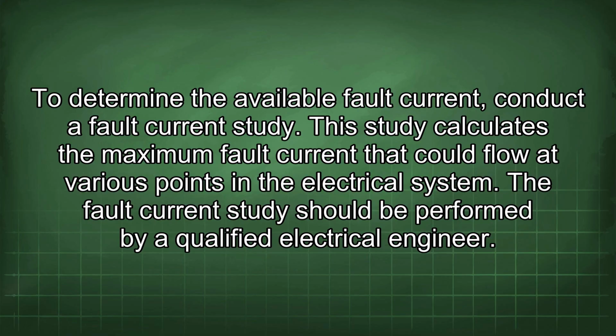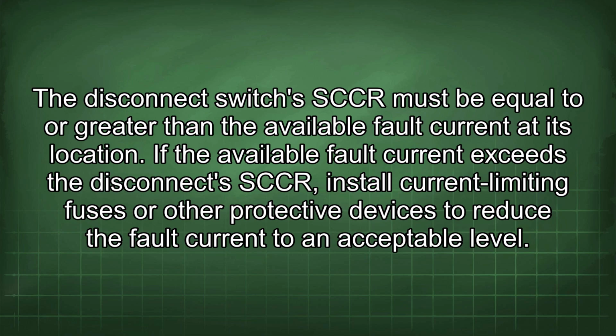This study calculates the maximum fault current that could flow at various points in the electrical system. The fault current study should be performed by a qualified electrical engineer. The disconnect switch's SCCR must be equal to or greater than the available fault current at its location. If the available fault current exceeds the disconnect's SCCR, install current limiting fuses or other protective devices to reduce the fault current to an acceptable level.